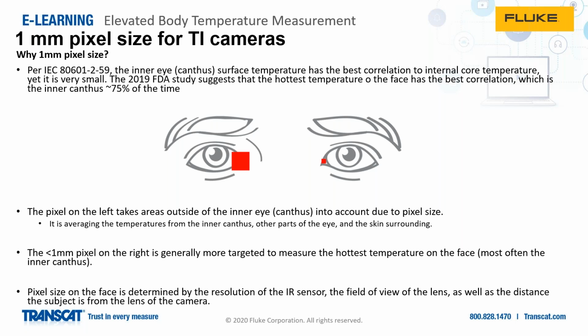So again, per that 80601 standard, the inner eye, or the canthus, as we saw in the study, is typically the hottest point on the face, and the hottest point on the face typically correlates best to the internal body temperature. About 75% of the time that's found on the inner canthus. But the inner canthus itself is very small in comparison to everything on the face. You'll notice in the crude picture that we have here, if your pixel size is the size of the one on the left, you're averaging temperatures amongst other parts of the eye that are not strictly the inner canthus, whereas on the right, that pixel size allows us to pick out just the inner canthus and get as accurate a temperature measurement of the inner canthus as possible.